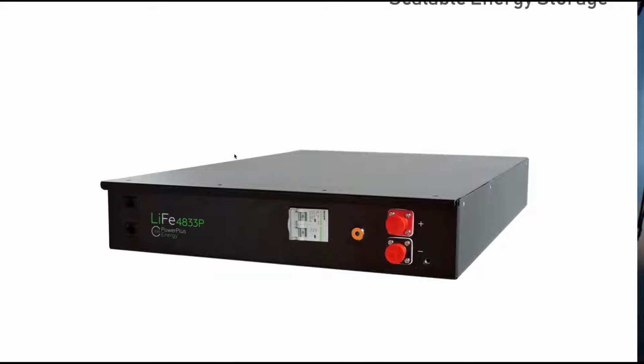But at the end of this is the end of the battery system, and we need to then have a main battery system isolator, or a means to isolate that whole battery system. So it could be some distance away, and therefore we've got that 2 meter consideration. So I'm just drawing, that's our main battery isolator here. And depending how far away the power conditioning equipment or inverter is, we may need another one at the PCE. So there you go. Both of these would give you a large amount of storage, but different characteristics.